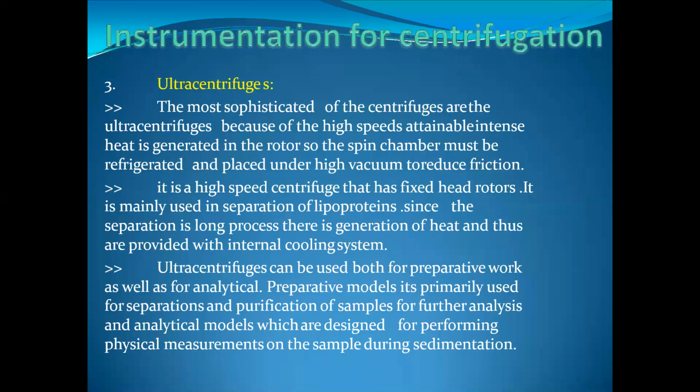Then ultracentrifuges. The most sophisticated of the centrifuges are the ultracentrifuges. Because of the high speed attainable, intense heat is generated in the rotor, so the spin chamber must be refrigerated and placed under high vacuum to reduce friction. It is the high speed centrifuge that has fixed head rotors. It is mainly used in separation of the lipoproteins.